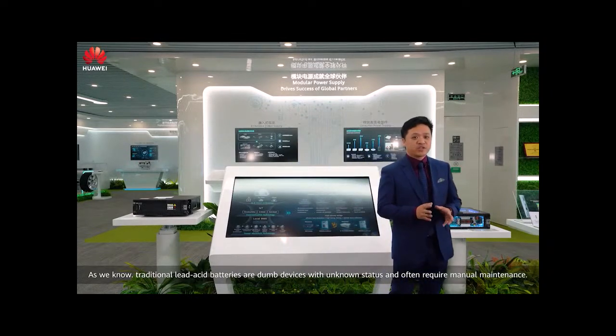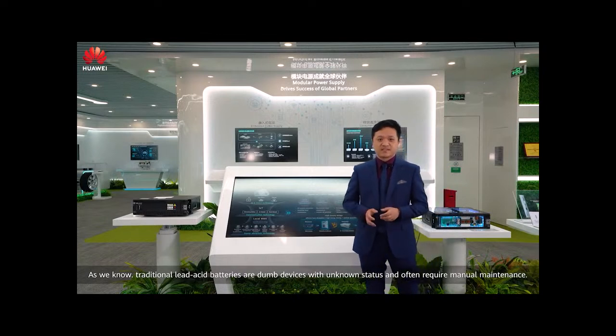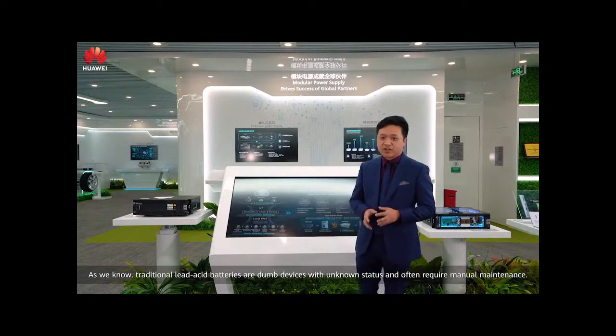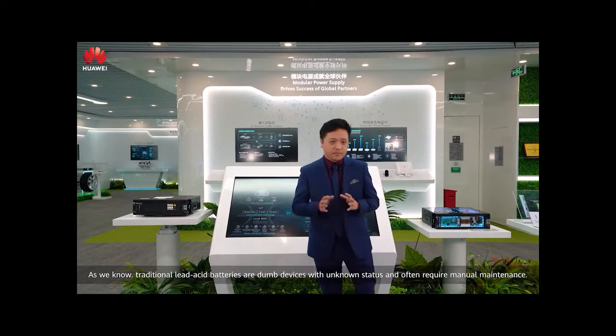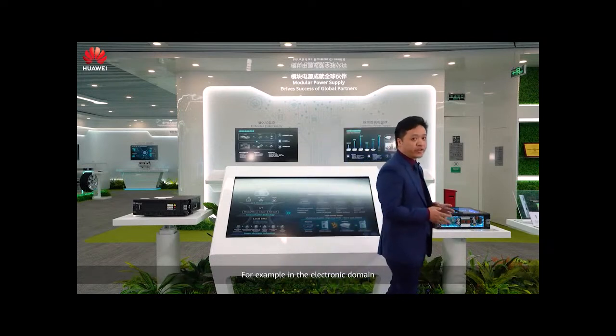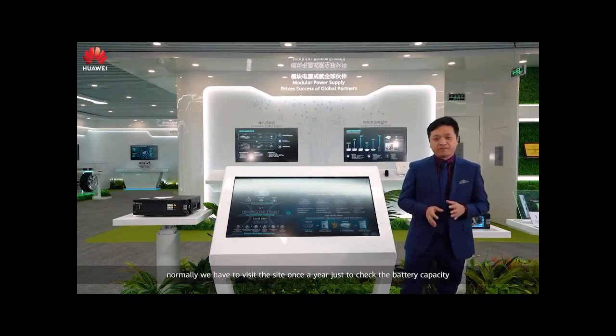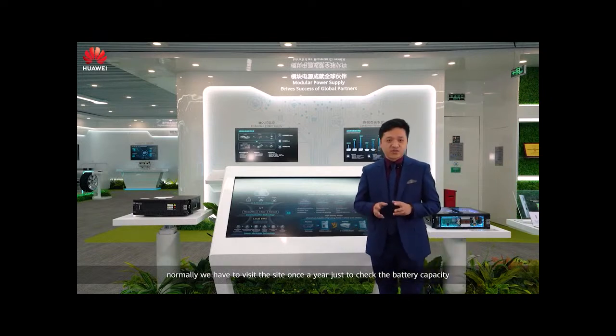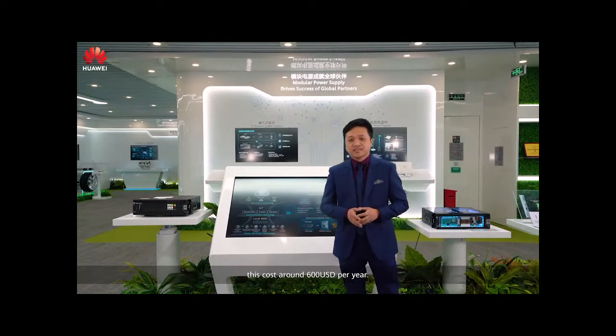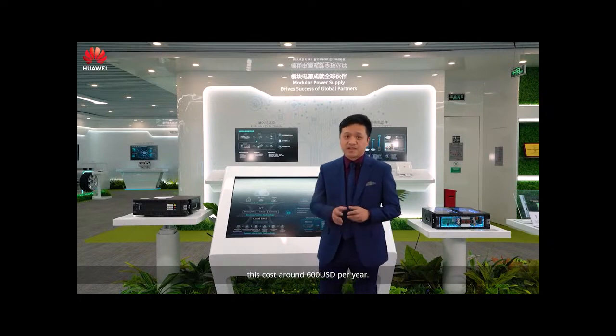Traditional lead-acid batteries are dumb devices with unknown status and often require manual maintenance. For example, in the electronic domain, usually we have to visit the site once a year just to check the battery capacity. This costs around $600 per year.